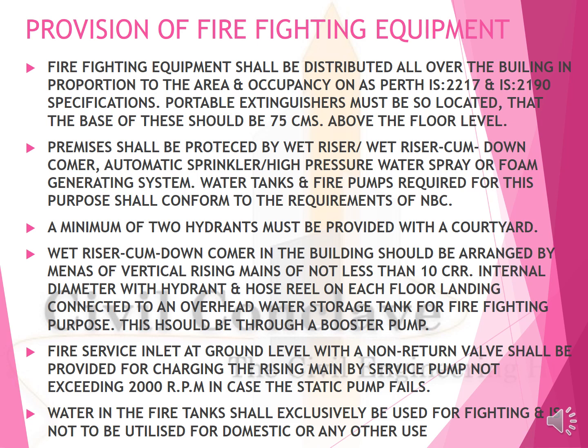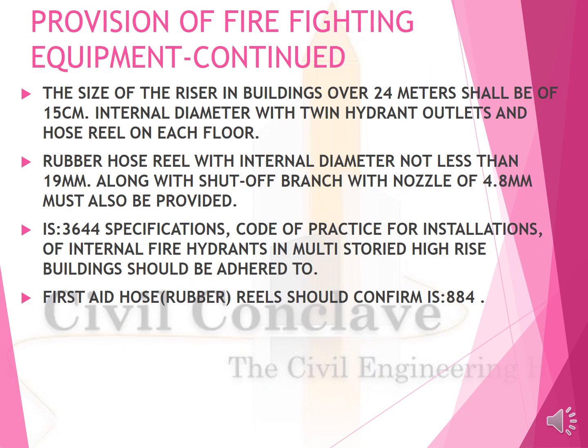The wet riser cum downcomer in the building should be arranged by means of a vertical rising main of not less than 10 cm internal diameter. A hose reel on each floor landing should be connected to an overhead water storage tank for firefighting purposes. This should be through a booster pump. A fire service inlet at ground level with a non-return valve shall be provided for charging the rising main by a service pump not exceeding 2000 RPM in case the starting pump fails. Water in the fire tank shall be used exclusively for firefighting and is not to be utilized for domestic or industrial uses.